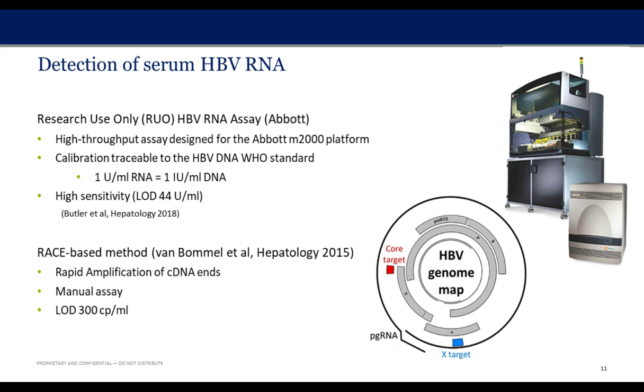To facilitate this research, Abbott has developed an HBV RNA assay that is highly automated on the M2000 platform. We designed the assay to be high-throughput, reproducible, and precise, with excellent sensitivity and a limit of detection of about 44 units per milliliter. We calibrated our HBV RNA units to the WHO DNA standard for a frame of reference. We also compared this test to the existing manual method published in van Bommel et al., a RACE method — rapid amplification of cDNA ends — which has a limit of detection of about 300 copies per milliliter and is quite labor intensive.